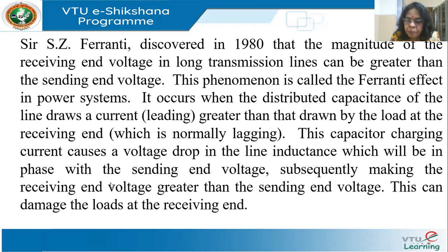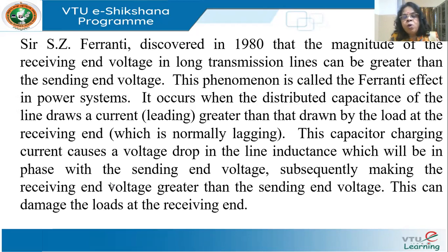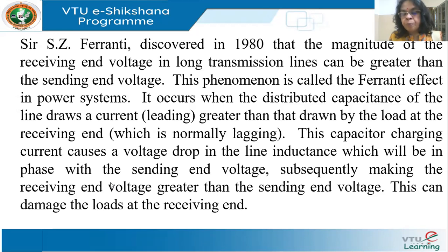If you take a transmission line, it has inductance and also capacitance between the conductor and ground. From our basic knowledge of electrical engineering, we know that a capacitor draws a leading current — the current drawn by the capacitor leads the voltage by 90 degrees. Inductors draw a lagging current, or the current lags the voltage by 90 degrees. On analysis, it was discovered that this capacitor charging is the reason for the Ferranti effect. If the receiving end voltage looks higher, it may damage equipment because equipment is designed for a particular voltage.